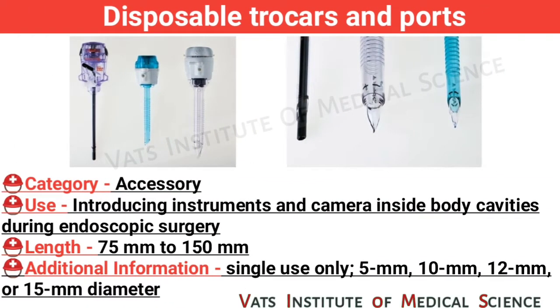Disposable trocars and ports. Category: accessory. Use: introducing instruments and camera inside body cavity during endoscopic surgery. Length: 75 mm to 150 mm. Additional information: single use only, available in 5 mm, 10 mm, 12 mm, or 15 mm diameter.